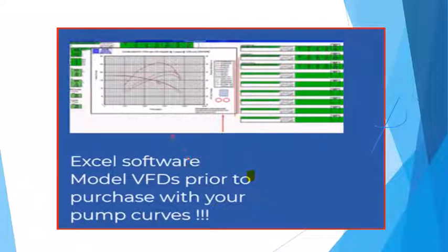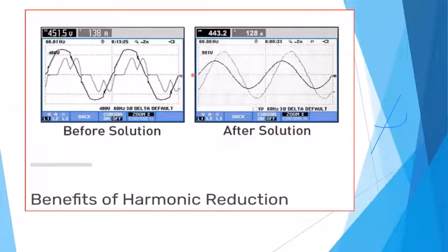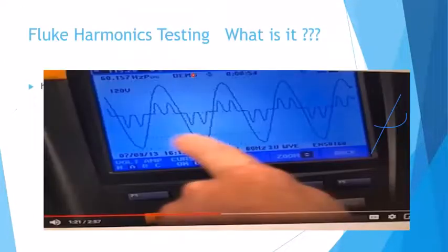So this is a software that, if you send me an email, I'll send you a link to a guy at the pumping efficiency group out of Australia, who has actually created this very unique software. It basically lets you put in various speed characteristics. You put in the original pump curve so that you can actually determine, are we staying at that peak performance point?